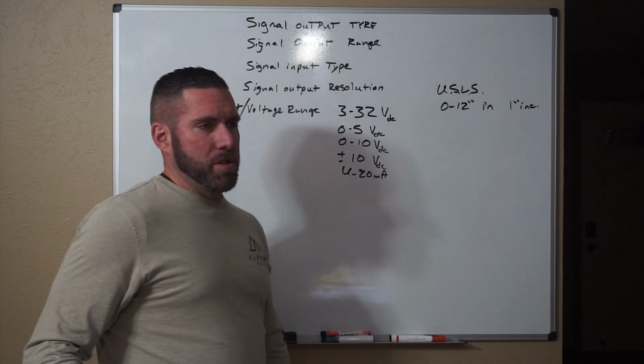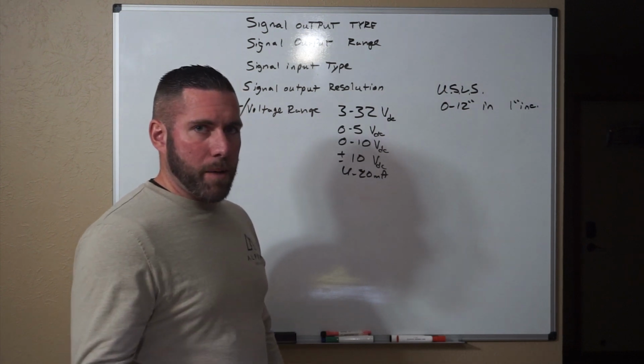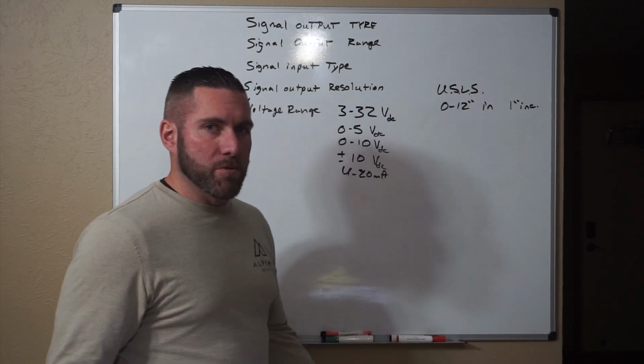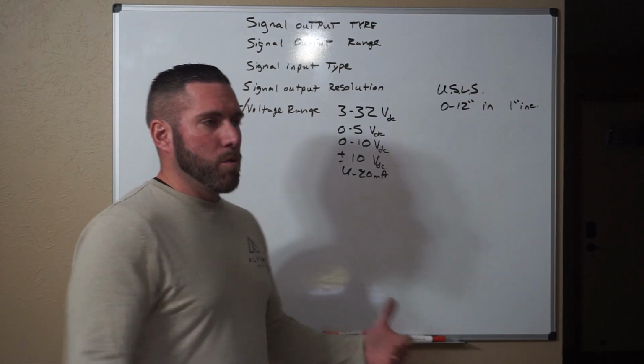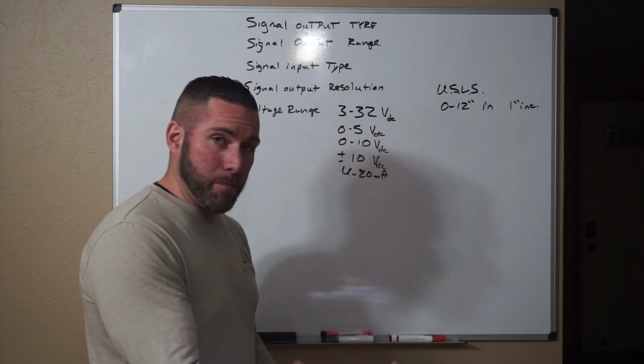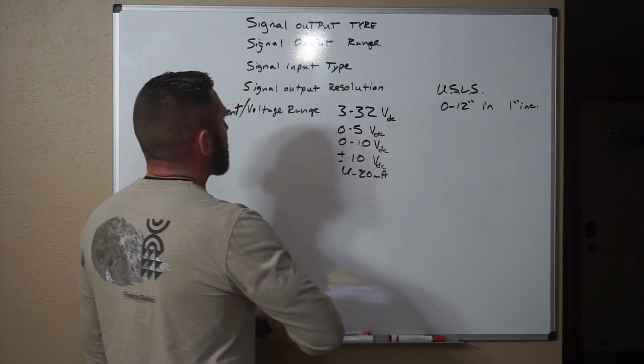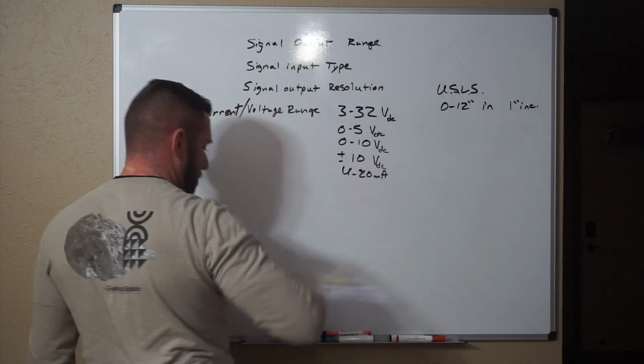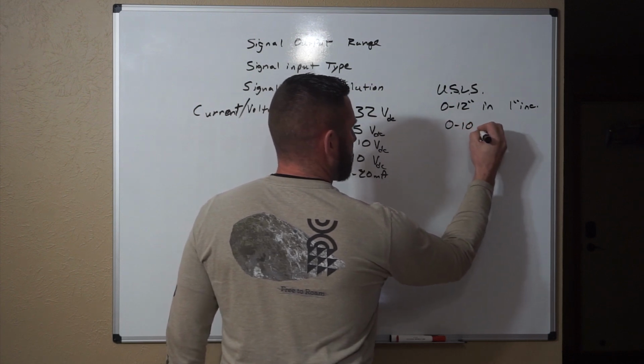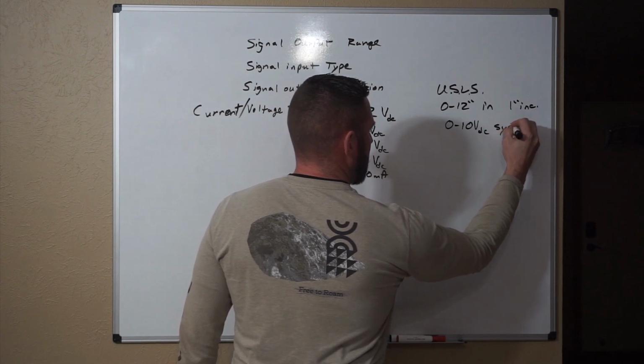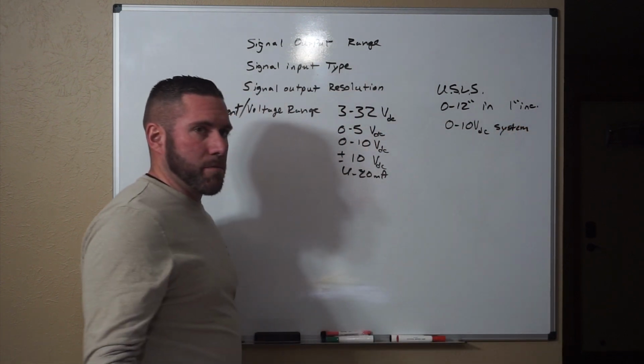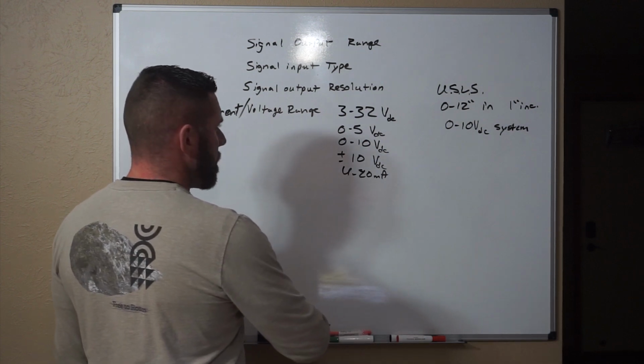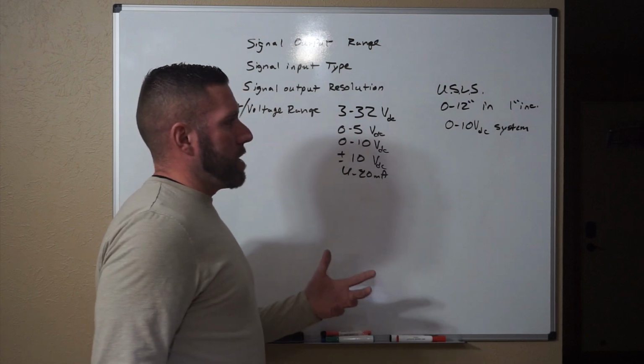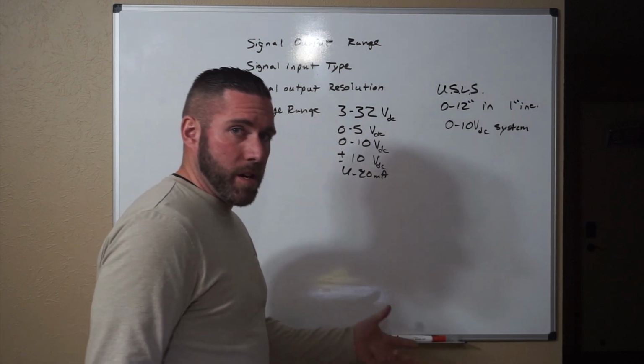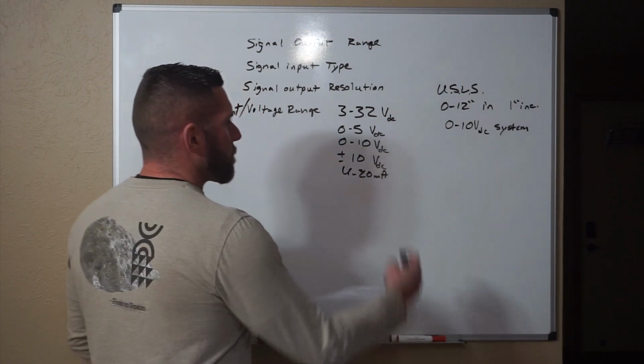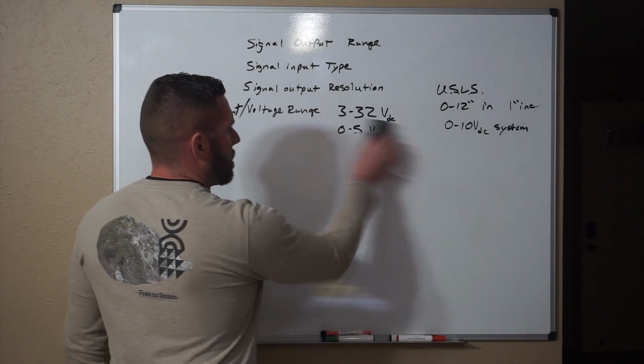So signal output type, we'll say we're going to feed it back to a module, and that module is what is going to populate the plant computer system. Well, we have to know what that module receives. Do we want it in 4 to 20? Do we want it in 0 to 10? What does the module receive from its minimum to maximum range of signal input type at the processor? So for signal input type, we'll say it's feeding back to a 0 to 10 volts DC system. And that's what's actually going to be reading what's coming off of the sensor. So when it comes back as a 0 to 10 volt system, what we want to be able to do is, first of all, what's going to be the supply power, and also what is going to be the receive back. So when we pick this out, let's get some of this stuff out of the way.